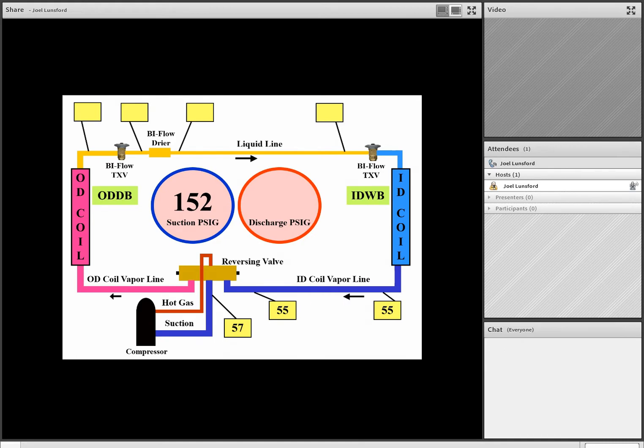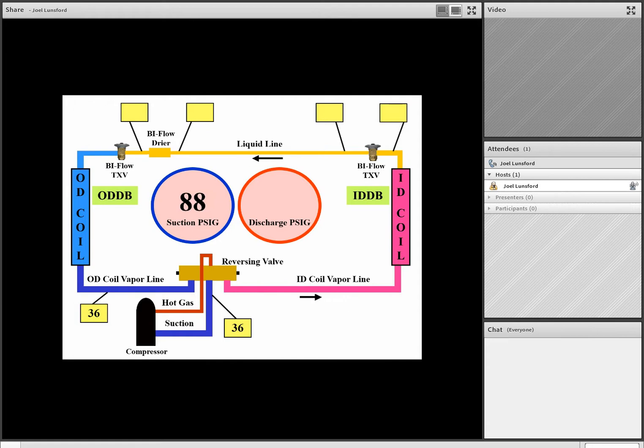Now in this example, we see that we have an R410A call, but we have switched modes from cooling to heating mode. But that's okay. Remember, team, superheat always applies to the cold coil. So in this example, we see the outdoor coil is cold because we're in the heating mode of operation, but superheat still applies. So let's do this example together. At 88 pounds of suction pressure for 410A, we see that we have a temperature conversion of about 25 degrees. However, the temperature of the physical suction line, the outdoor coil vapor line coming off the outdoor coil, is 36 degrees.